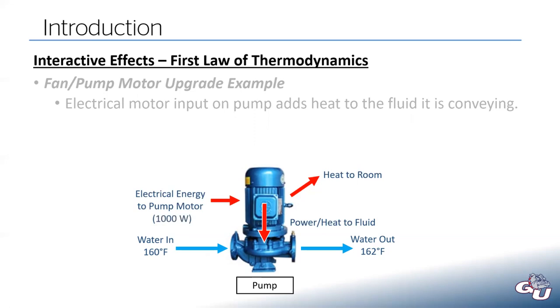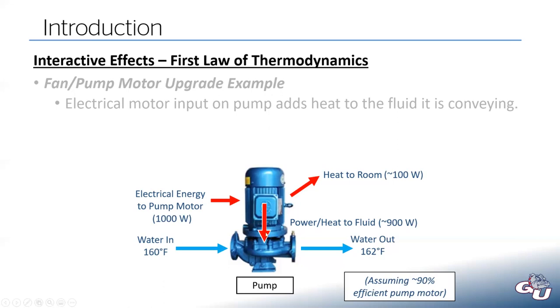So if we're going to run this motor with 1,000 watts of power, let's say about 900 watts of that is conveyed into the fluid, and you're going to have about 100 watts come off as heat just from the inefficiency of the motor. And so this is assuming about a 90% efficient motor. But what this does is this 900 watts that we have just transmitted into the fluid will now heat up the water a bit. So if that water's coming in at 160 degrees, it's going to leave a little bit warmer. You know, in this case, 2 degrees. And maybe that's significant, maybe it's not.